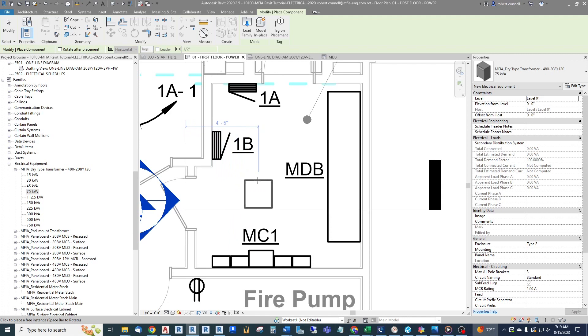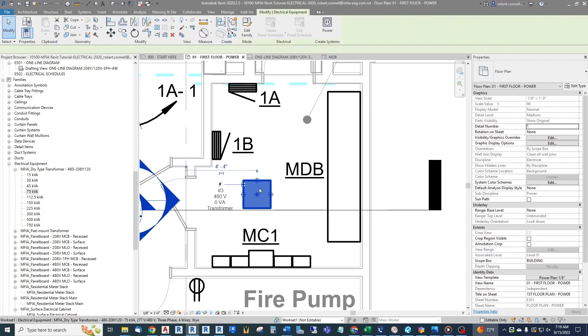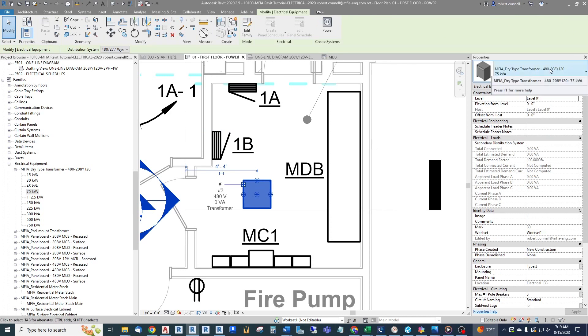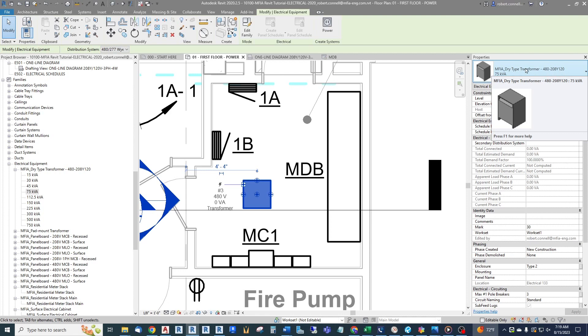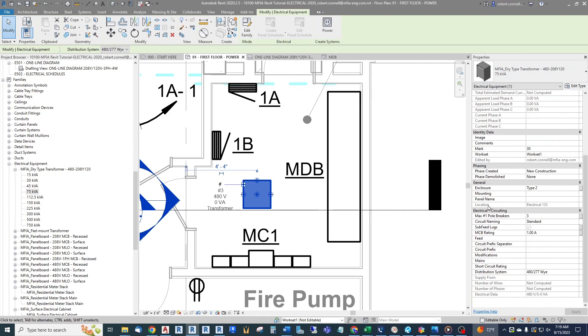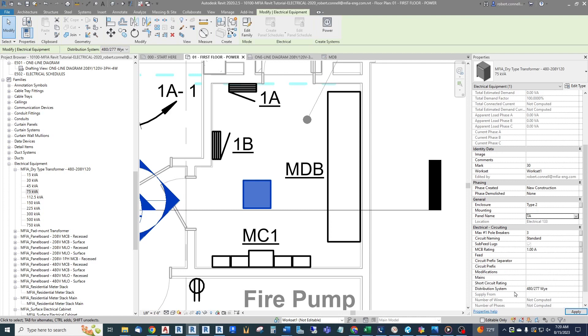There we go — this is the transformer; where my cursor is points to the back center of it. I'll set it in the middle of the room since this is just a sample. Clicking on it, we see it's a dry type 480 down to 208Y/120, three-phase transformation. Similar properties — we can give it a panel name, let's call it 'TA'. It's set up for one three-pole sub-feed. The primary distribution system comes in automatically. What doesn't come in automatically is the secondary distribution system — the secondary voltage — and we need to remember to set that.